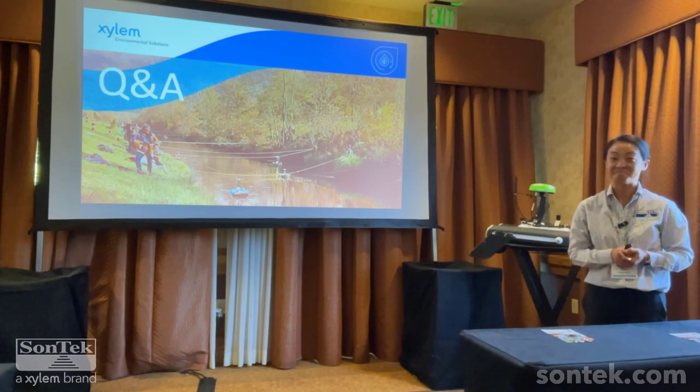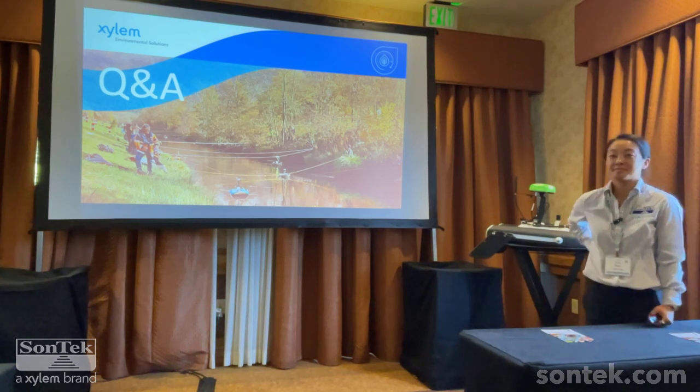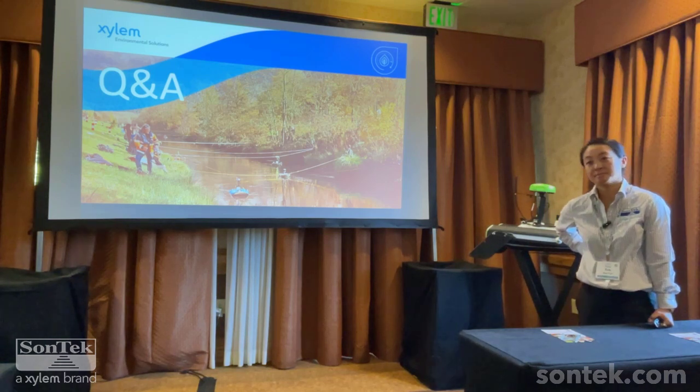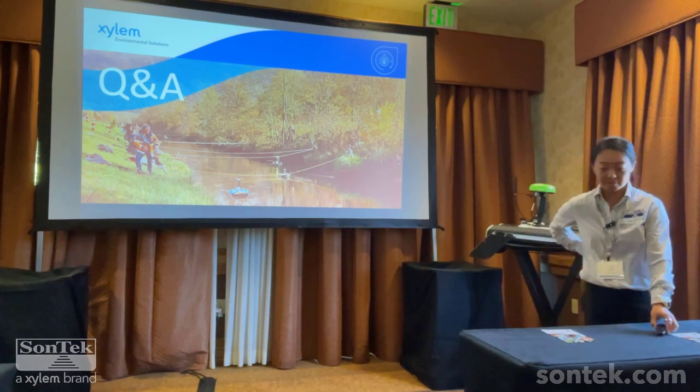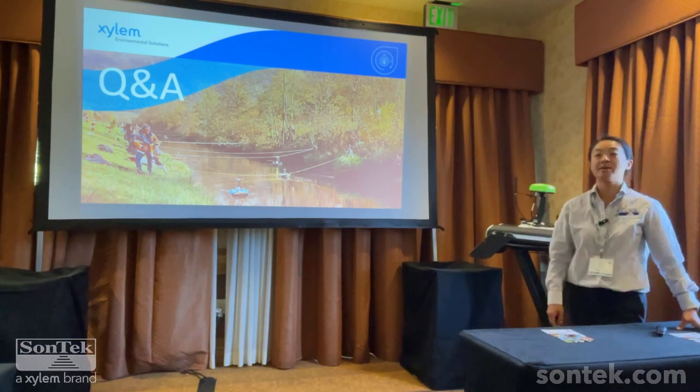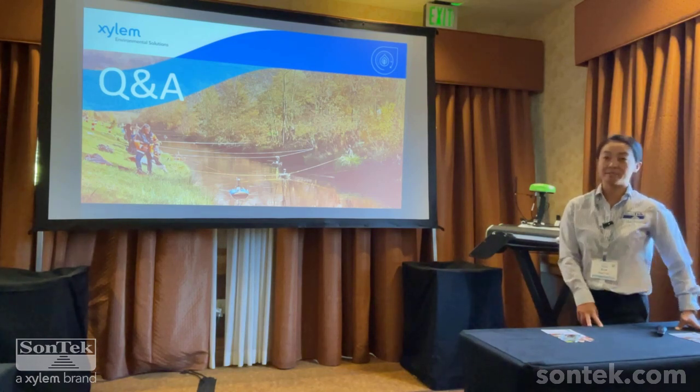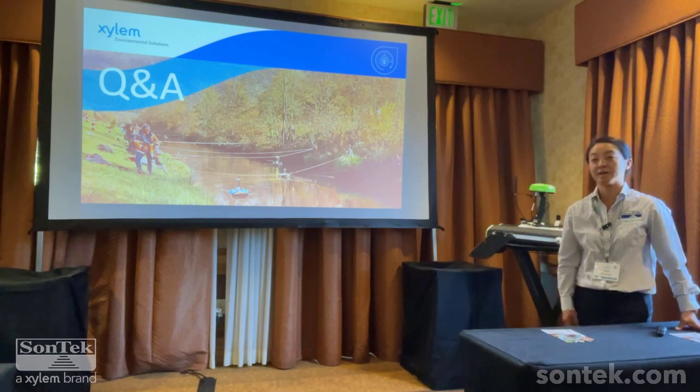I have a few questions. First, on the stationary measurement technique, is the single software, I don't remember the name, is it RSQ? Does that handle that as well as the moving boat? Yeah, that's a great question. So RSQ, that software platform, will have the moving boat method and stationary method embedded in the same software.